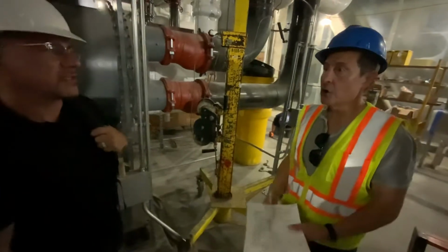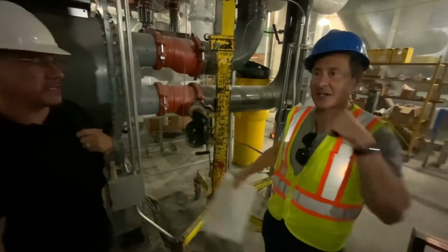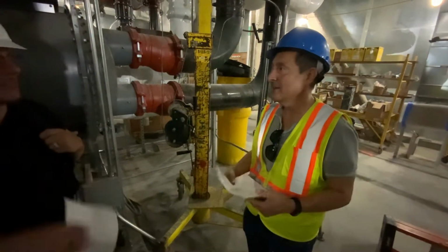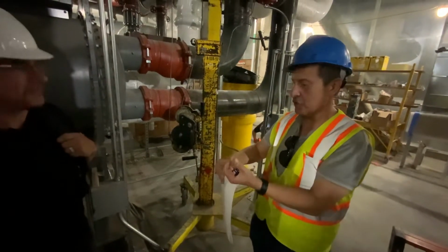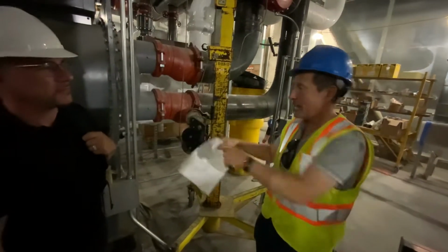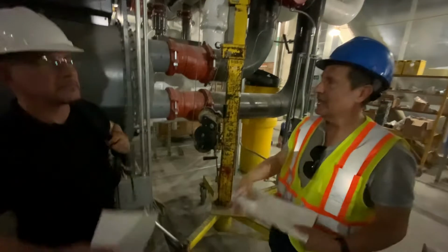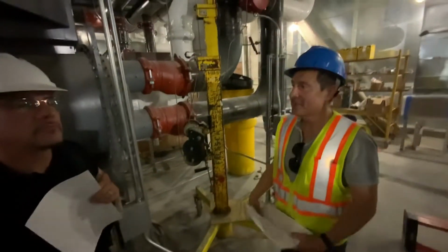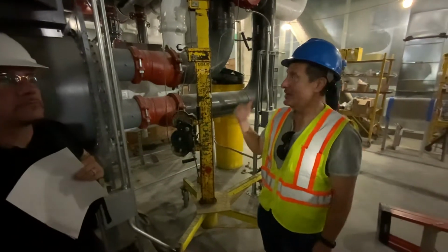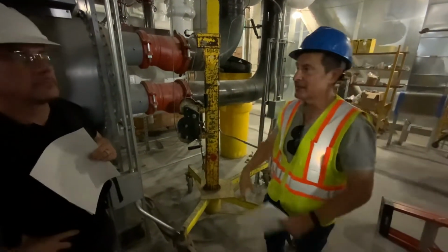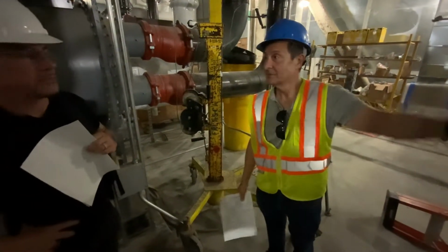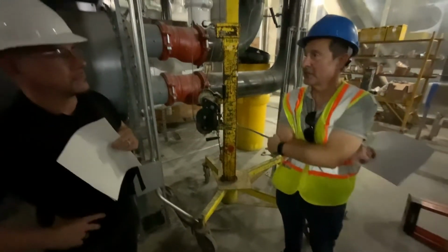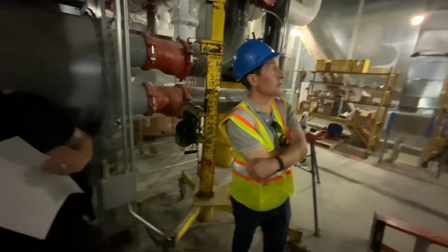Yep. The machine's going to go, holy cow, I got to catch up. It's going to try to catch up as fast as it can, but it's got inlet guide vanes to control, it's got a VFD to control, it's got the float, it's got refrigerant level. It can't react quick enough, so it's going to trip. So to prevent that from occurring, you demand limit it first, and then you turn on the other machine, then you release the demand. And same for the third, and vice versa when you go through the whole thing.